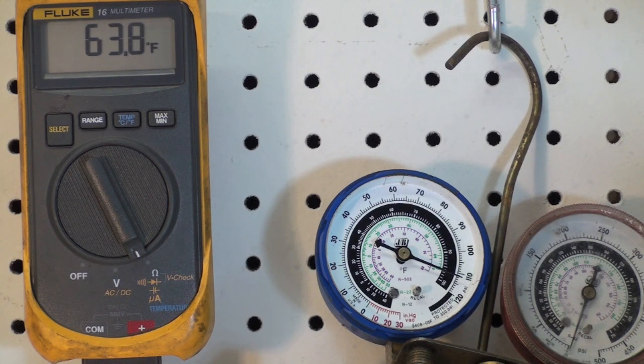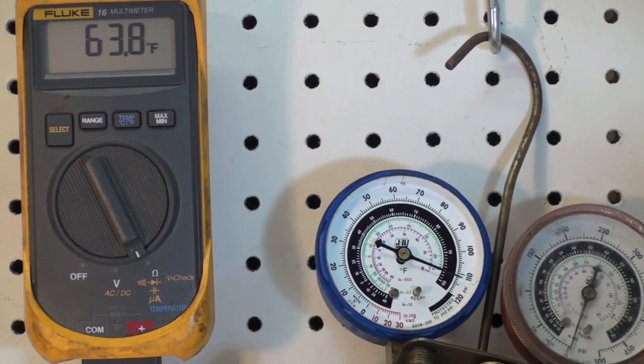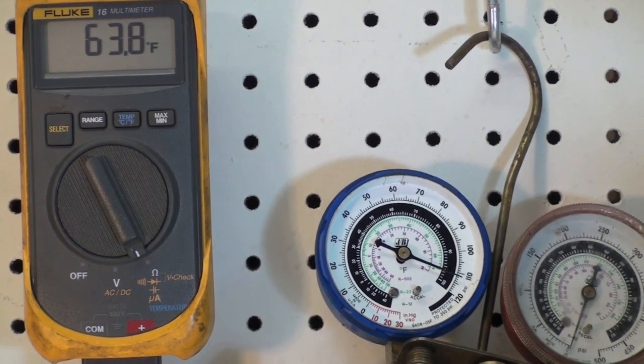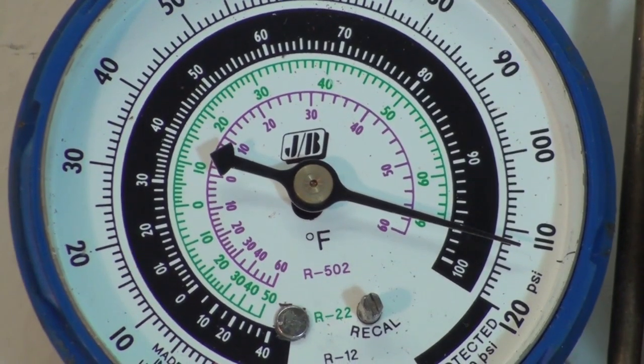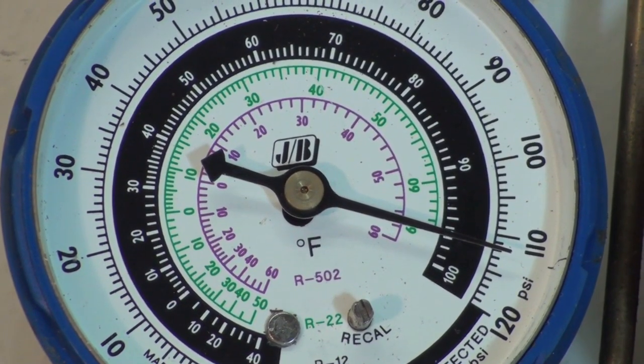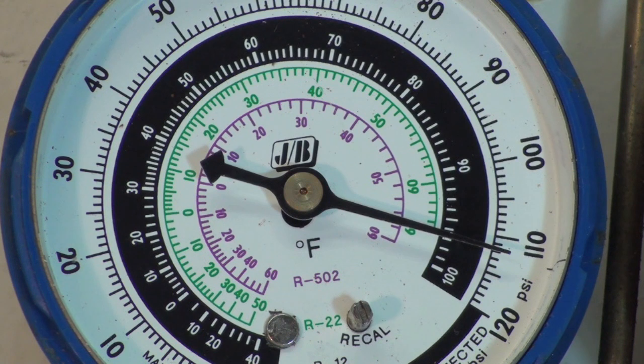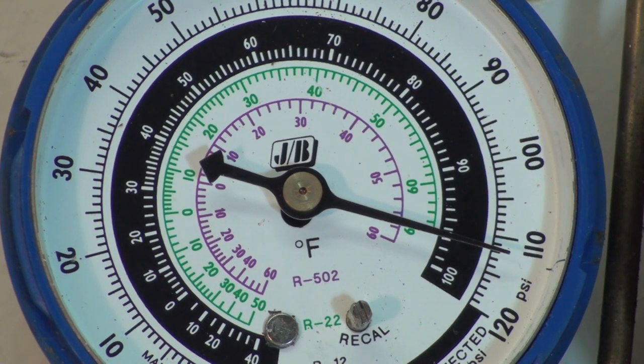You can buy dedicated electronic thermometers, some with two probes. Those are better than this because this just goes along with a multimeter. But let's see how close that 63.8 is to the actual pressure temperature. Now we're going to look at that on the gauge dials.